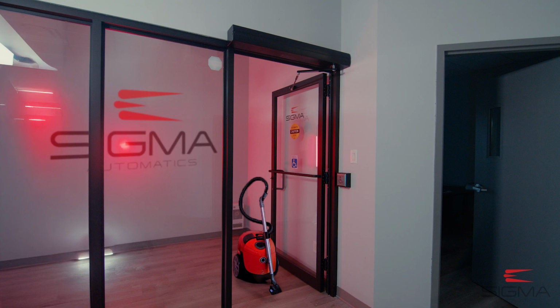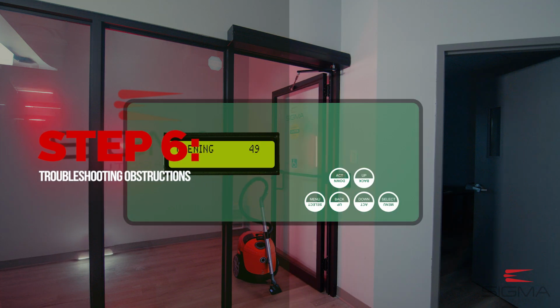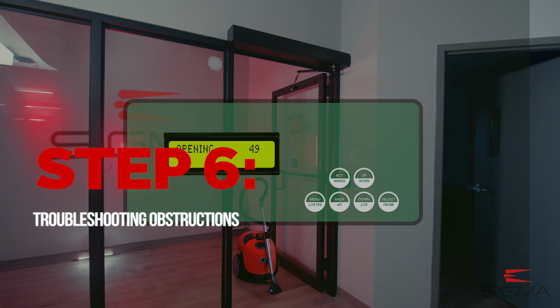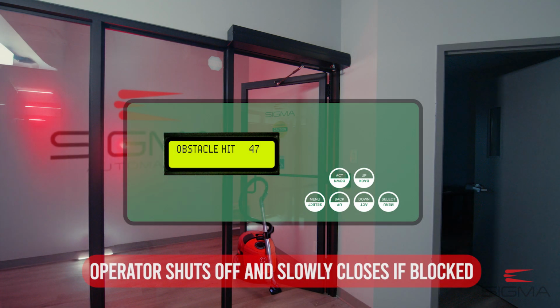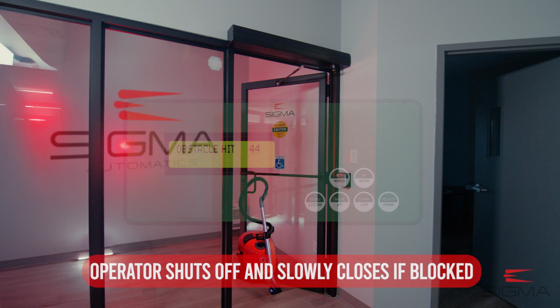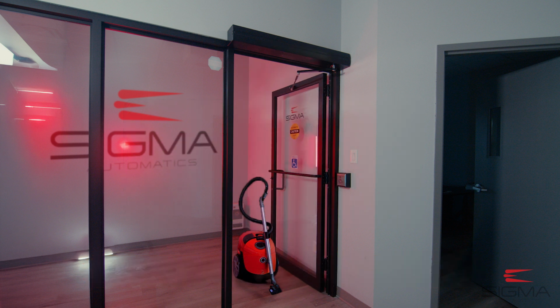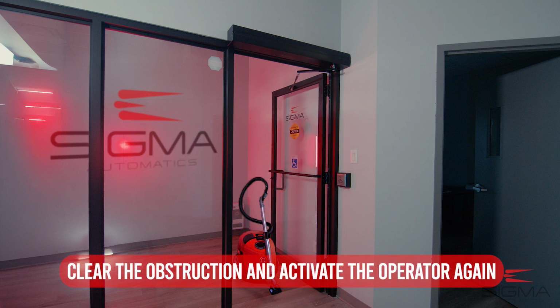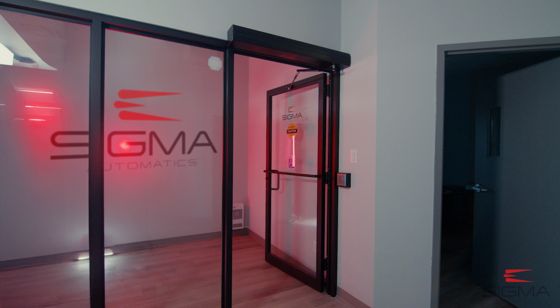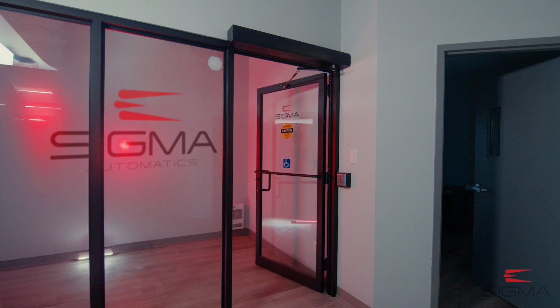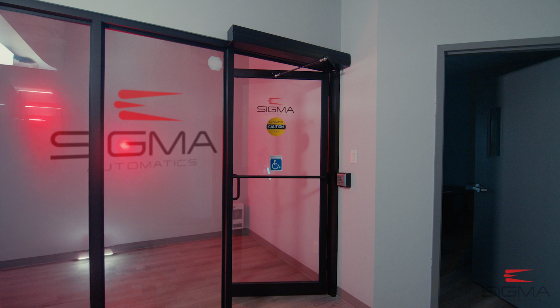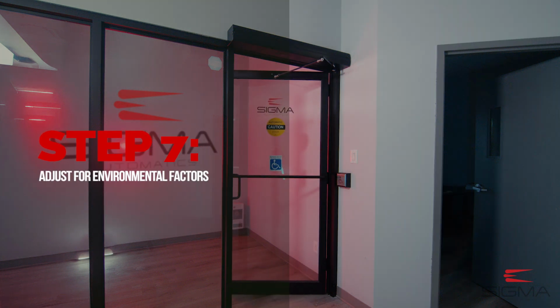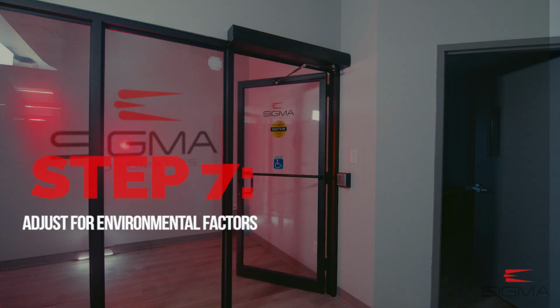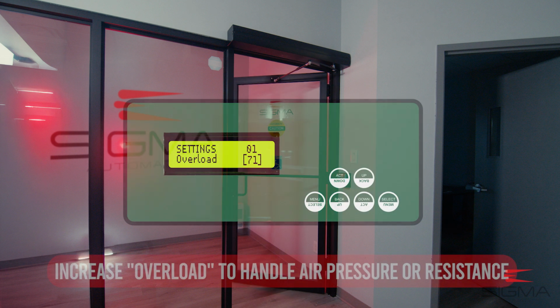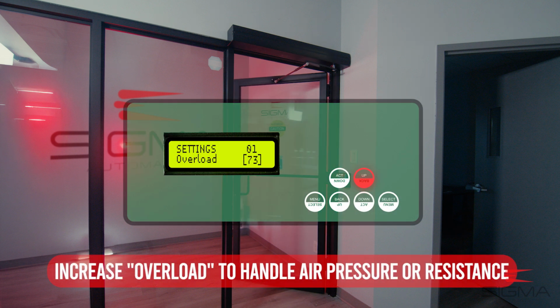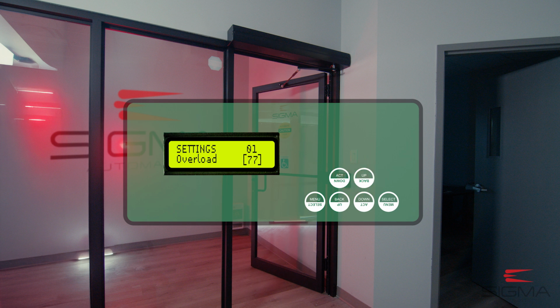After initial setup, common issues may include the door hitting obstructions or being affected by excessive air pressure. If the operator senses an obstruction, it will shut off and reset. Once the system is reset, you can activate it again once the obstruction is cleared. If the door struggles to open due to negative air pressure or other external factors, increase the overload parameter to give the motor more power to overcome resistance while staying within ANSI standards.